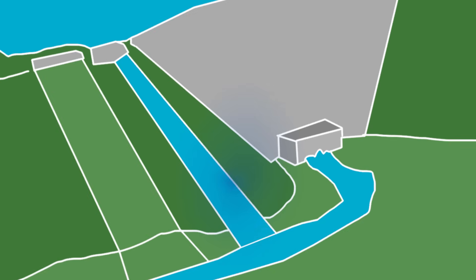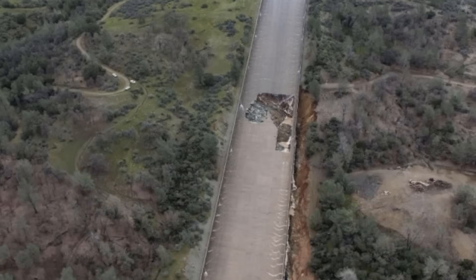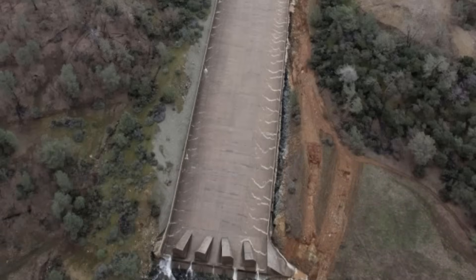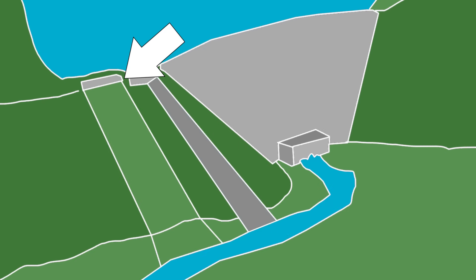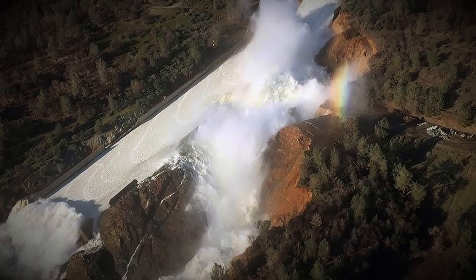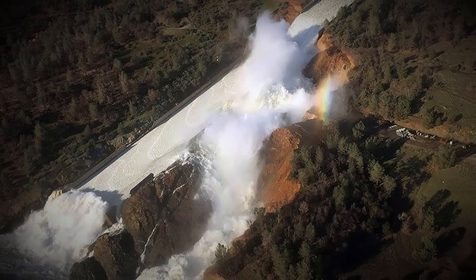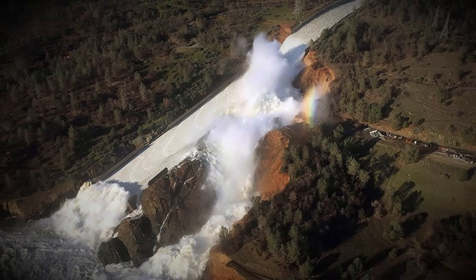Water was flowing off the side of the spillway, about a third to a half of the way down. Operators stopped the flow to the spillway and the crater was revealed — parts of the concrete lining had disappeared and erosion had begun at the failure point. This created a rock and hard place situation for the operators: do they continue using the clearly compromised spillway, or allow the basin to fill to the point it would overtop the emergency spillway, which could cause all the erosion issues mentioned in the 2005 re-licensing? They chose to keep using the main spillway, hoping a reduced flow rate wouldn't cause much more damage. The spillway gates were opened on the 9th of February and again water started flowing down, but the reduced flow was not enough to reduce the basin water level, and it slowly rose.